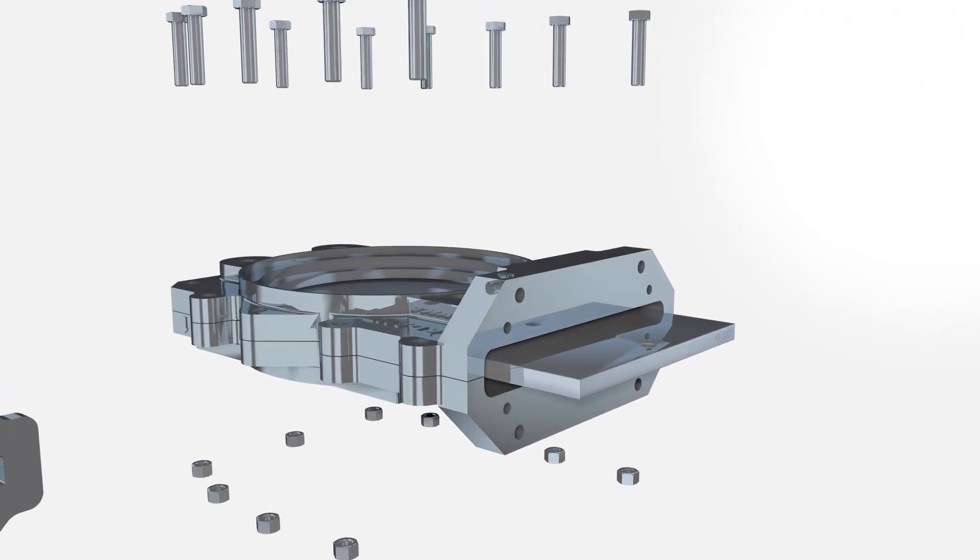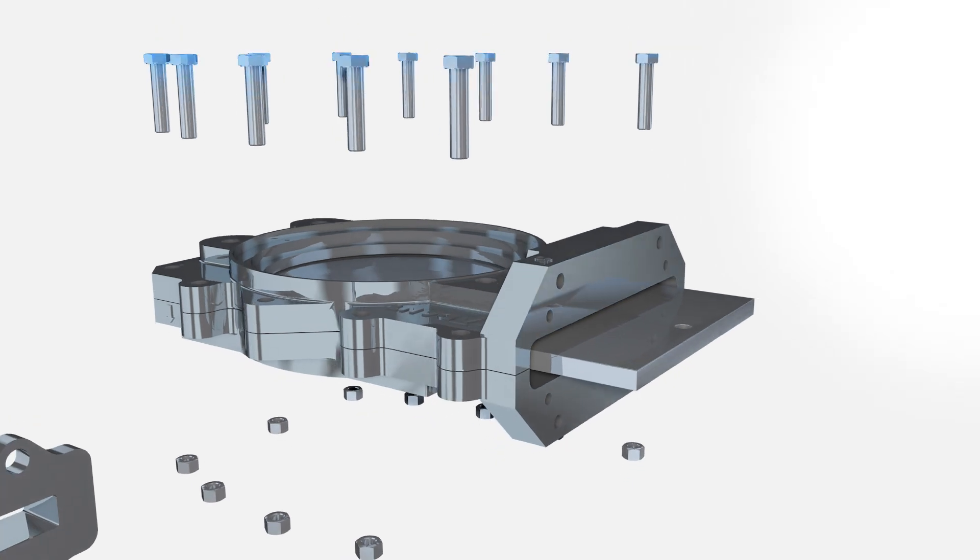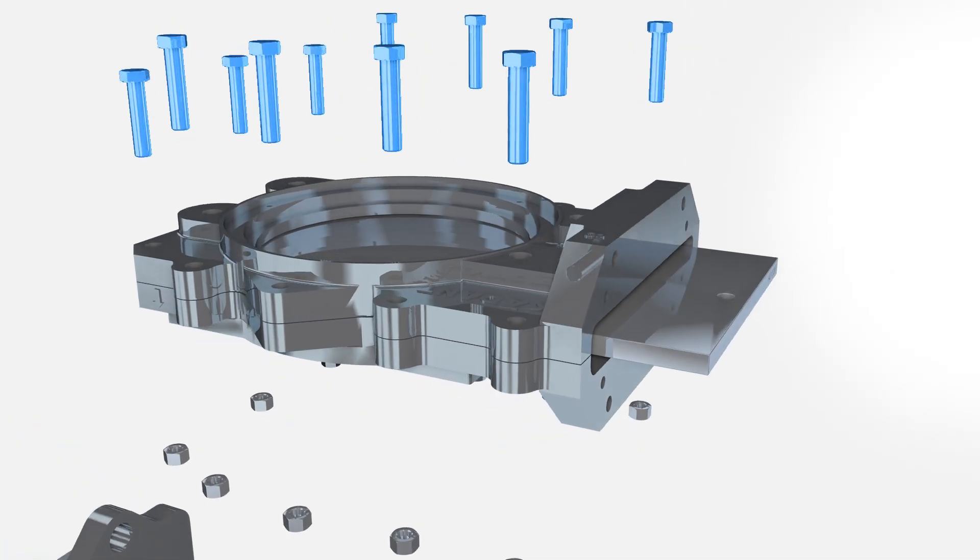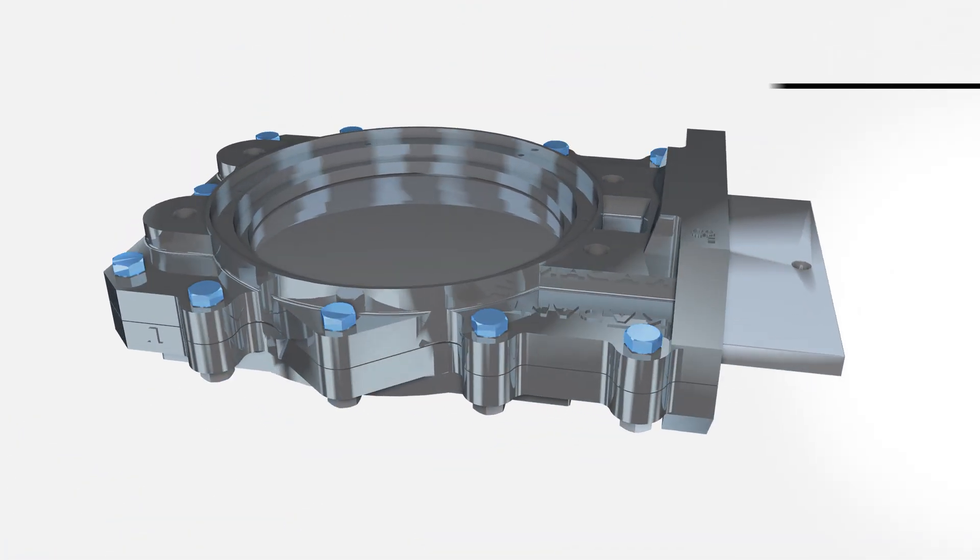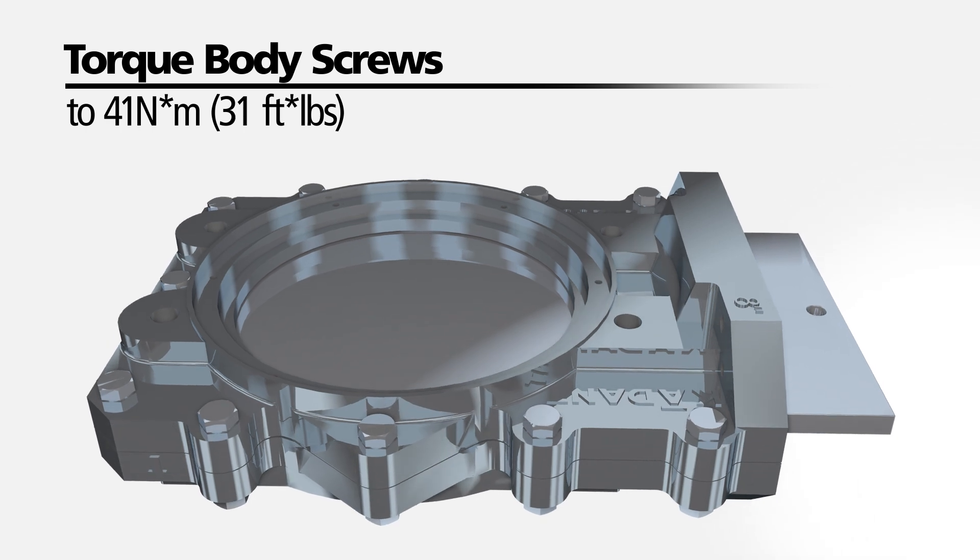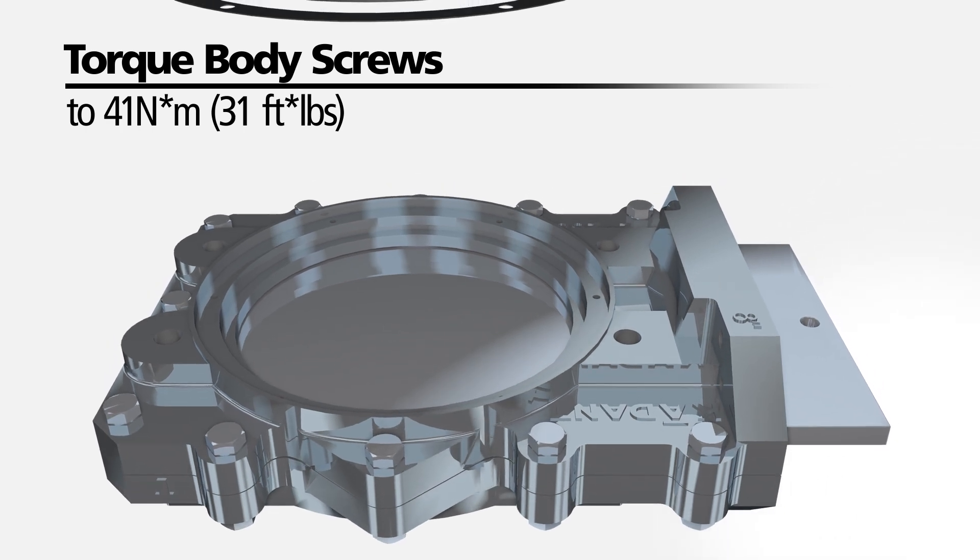Apply anti-seize lubricant to all threads and install the body screws and nuts. Torque the body screws to 41 Nm.